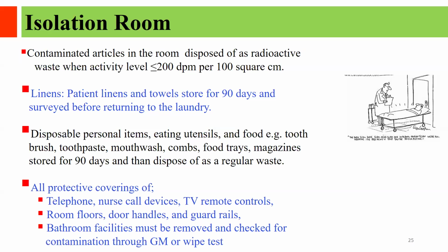Then comes nuclear medicine. We all know that thyroid cancer patients, when treated with iodine 131, have to be isolated or kept in a ward until the activity level comes down below the limit prescribed by the competent authority of the National Regulatory Authority. The contaminated articles in the room are disposed of as radioactive waste when the activity is less than this contamination level per 100 square centimeters. Whatever linens are generated, like patient linens and towels, are stored for 90 days and surveyed before returning to the laundry.